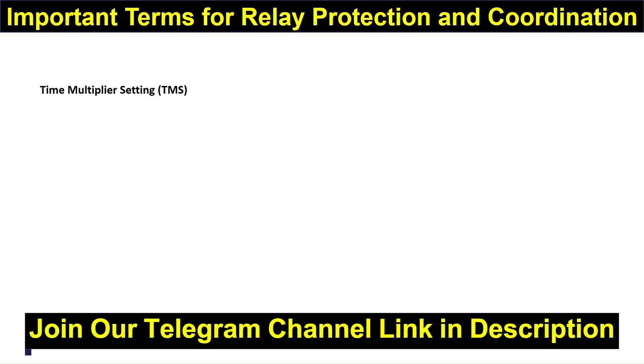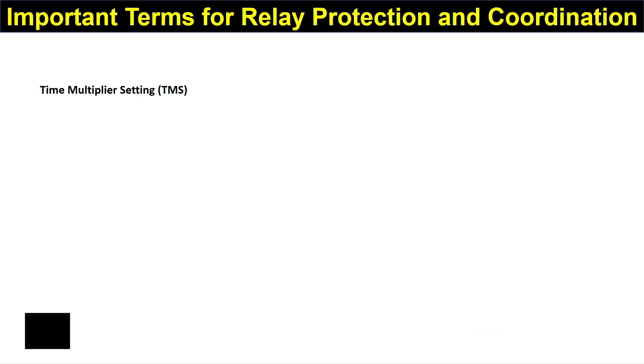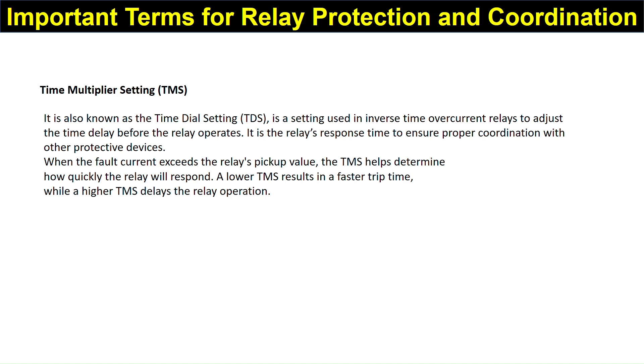The next term is Time Multiplier Setting, or TMS, also known as the time dial setting. It is a setting used in inverse time overcurrent relays to adjust the time delay before the relay operates. It ensures proper coordination with other protective devices when the fault current exceeds the relay pickup value.